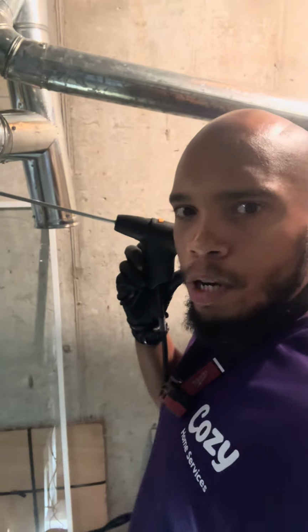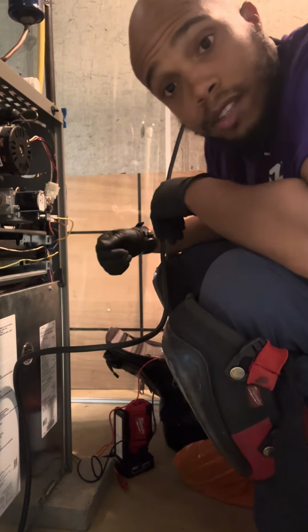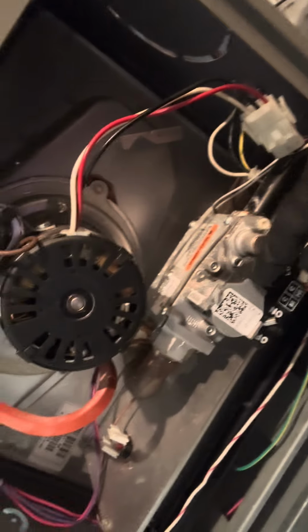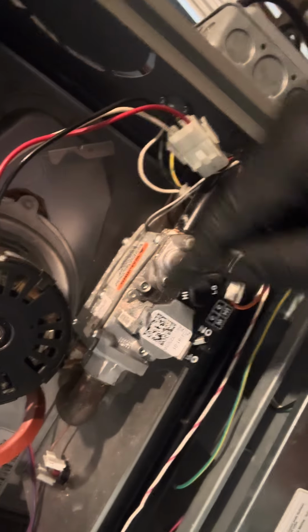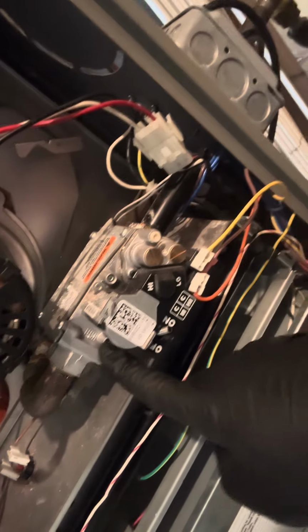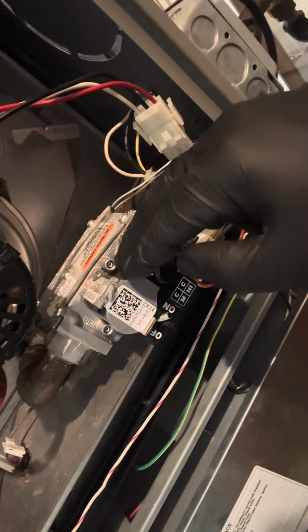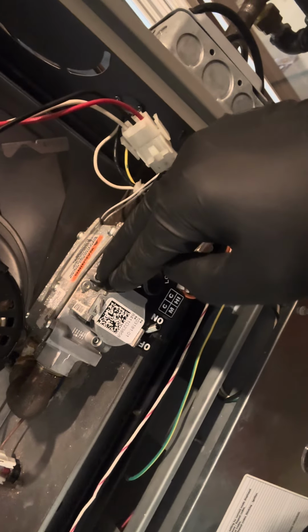What about the combustion analyzer? The thing we're going to be testing is the gas pressure. So here is your gas valve. This is a residential gas valve. You have 2 test ports. You can test the incoming gas pressure here, and you can test the outgoing gas pressure right here.